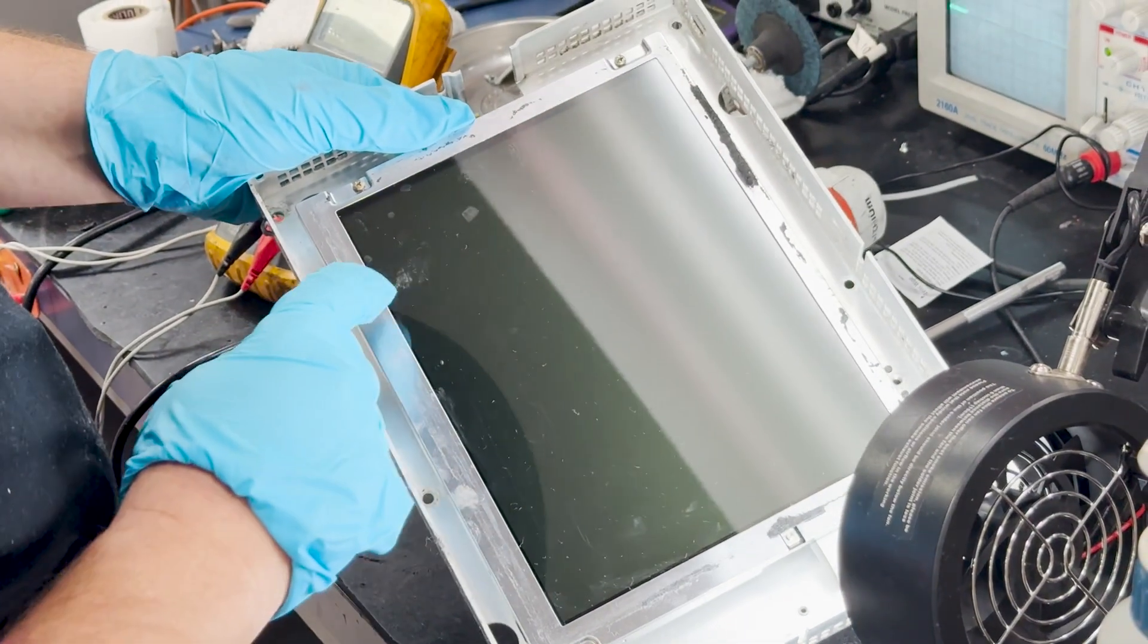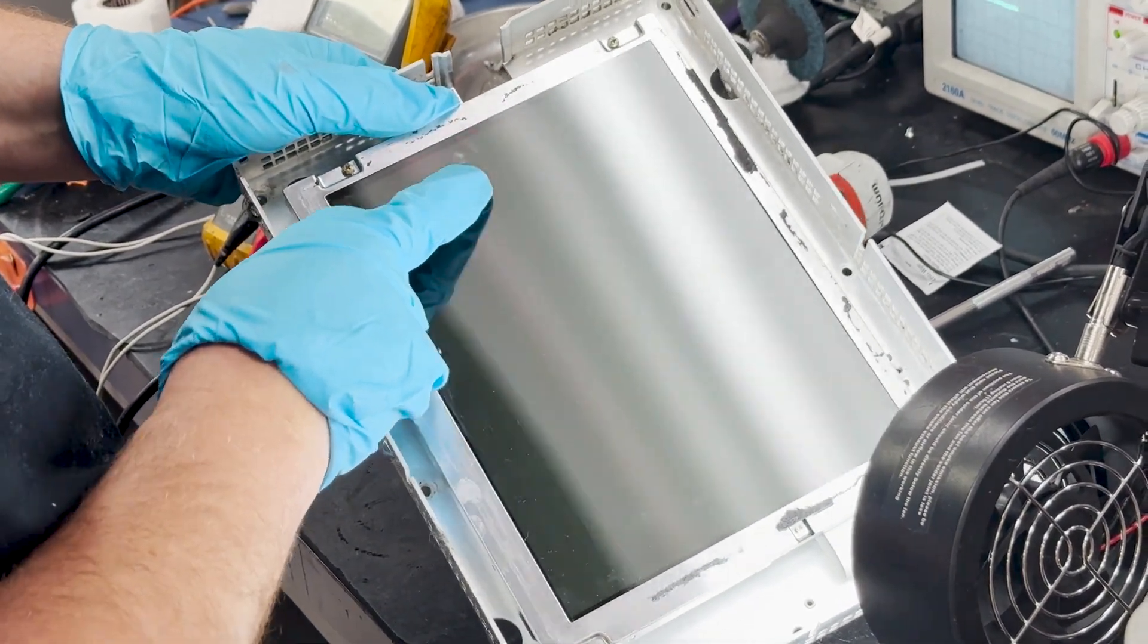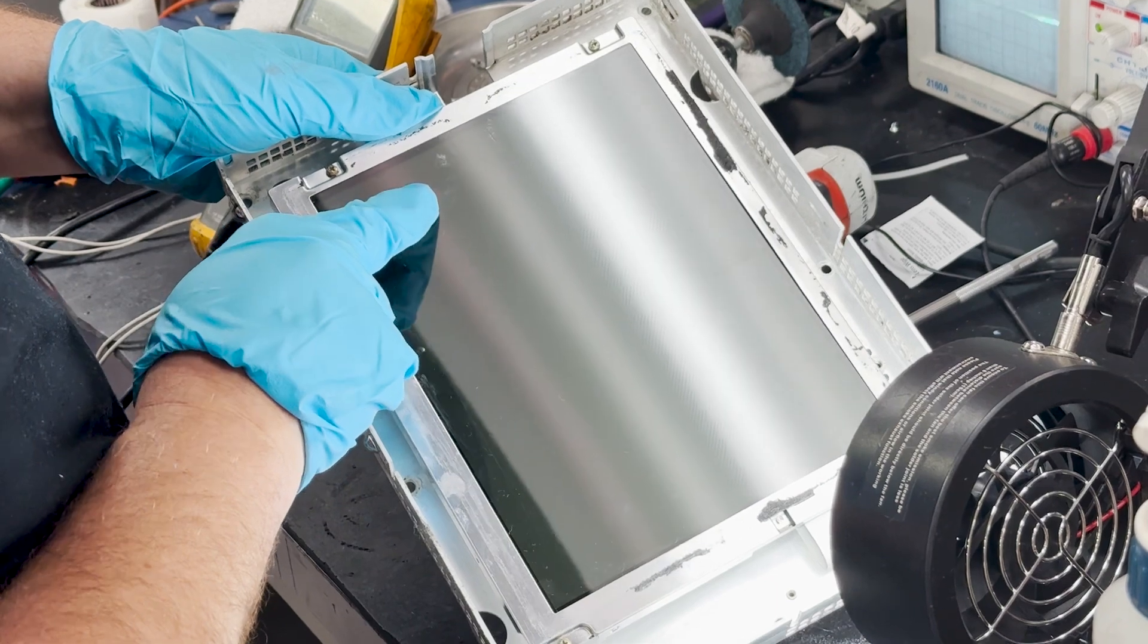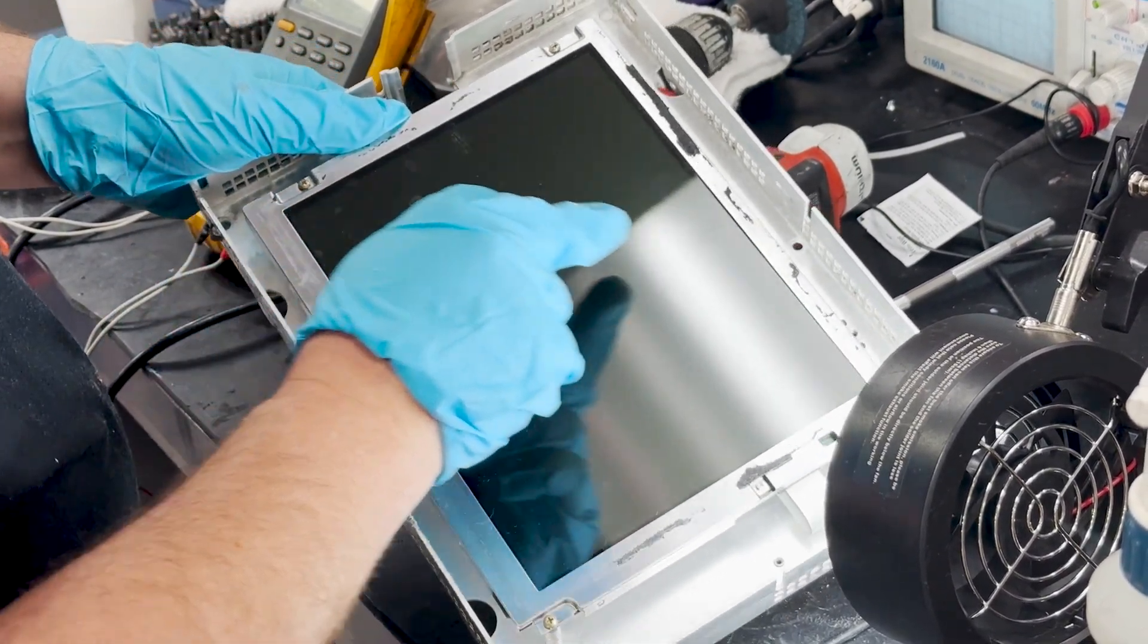While disassembling the unit, we discovered that water had penetrated the LCD panel. Although the LCD may still function with this level of moisture, the water spots could potentially impact the display quality over time. To ensure long-term performance and visual clarity, we will proceed with a complete LCD replacement.